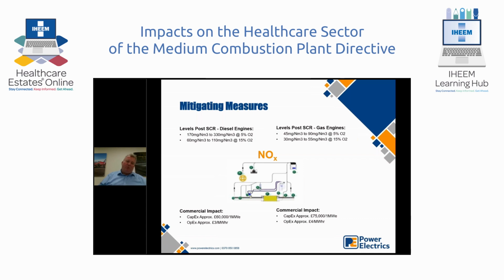The CapEx approximate cost is around £60,000 a megawatt for retrofit and also for new. New is obviously easier; to retrofit something in a plant room or onto a container has its issues and its problems, but can be overcome, no problem. The operational side for diesel is around £3 per megawatt hour. Most of that comes from the operational cost of the AdBlue and maintenance, although the maintenance on these systems is not a lot.